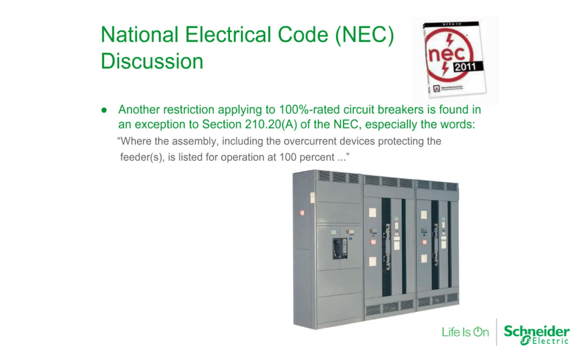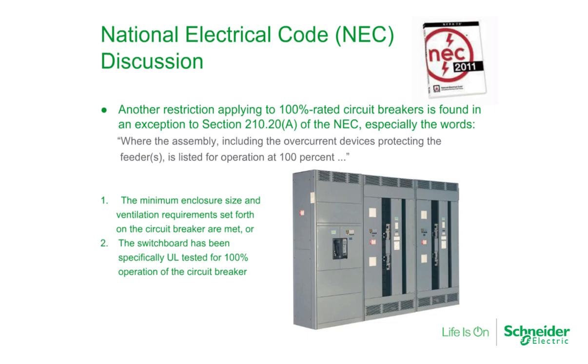Switchboard manufacturers do not label their enclosures as either 100% or standard rated. Instead, a switchboard is suitable to have 100% rated circuit breakers installed and applied at 100% if the minimum enclosure and ventilation requirements set forth on the circuit breakers are met, or the switchboard has been specifically UL tested for 100% operation of the circuit breaker. In enclosures supplied with standard rated circuit breakers, it is not necessarily possible to replace a standard rated circuit breaker with a 100% rated circuit breaker and obtain 100% rating. The enclosure must meet the minimum enclosure and ventilation requirements and be marked as such.